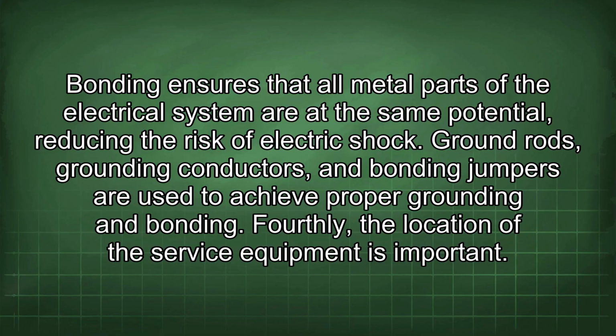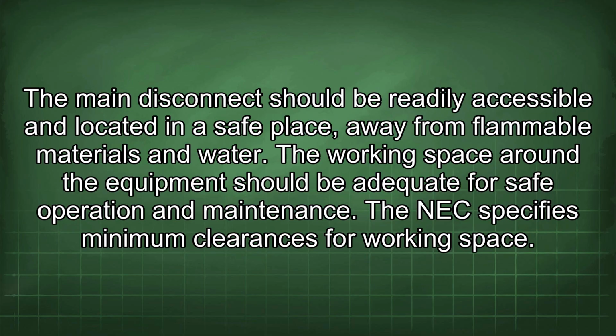Fourthly, the location of the service equipment is important. The main disconnect should be readily accessible and located in a safe place, away from flammable materials and water. The working space around the equipment should be adequate for safe operation and maintenance. The NEC specifies minimum clearances for working space.